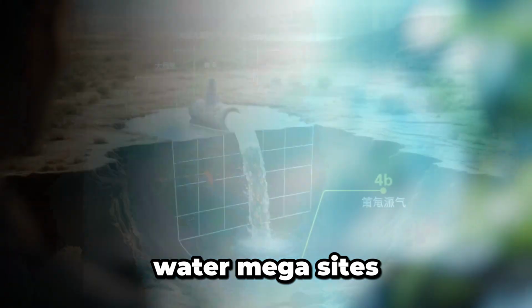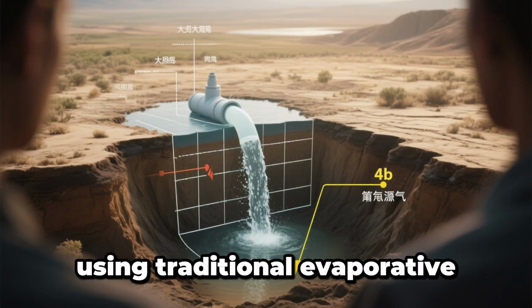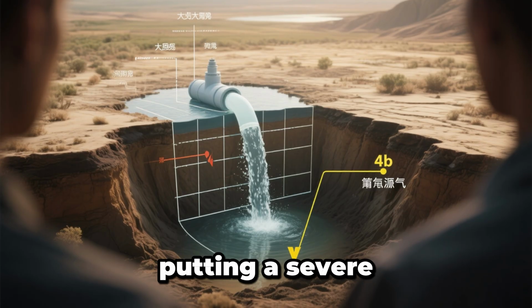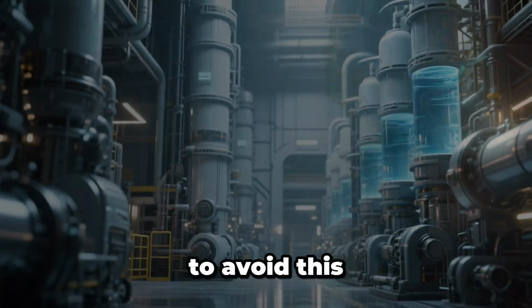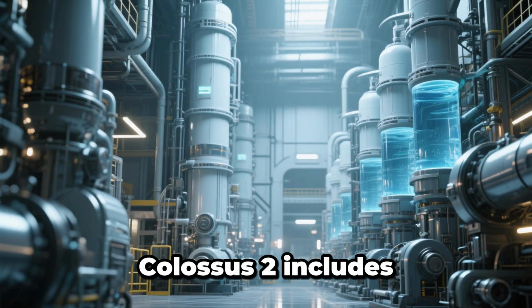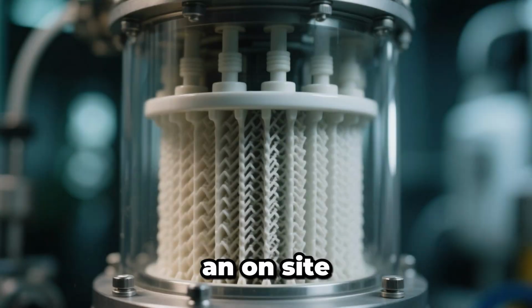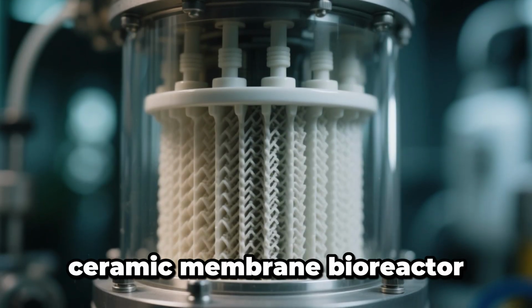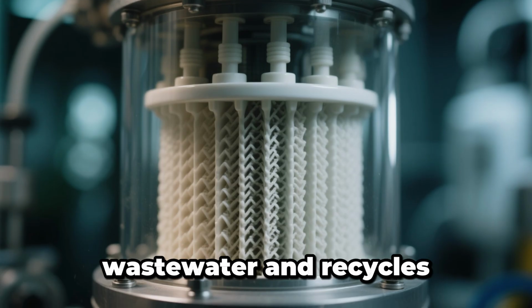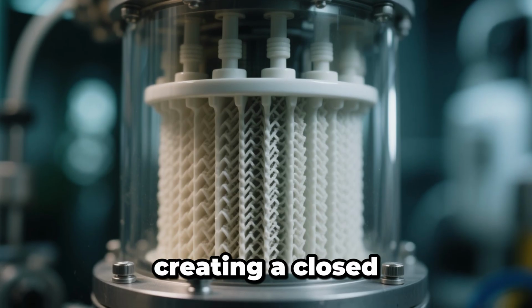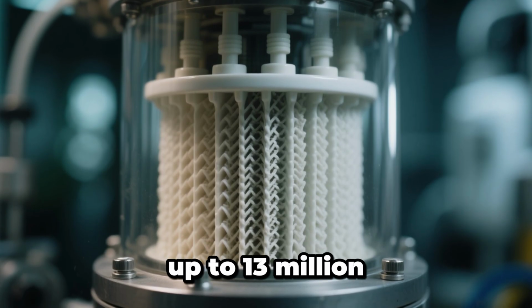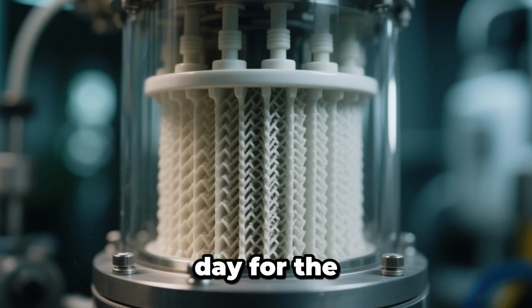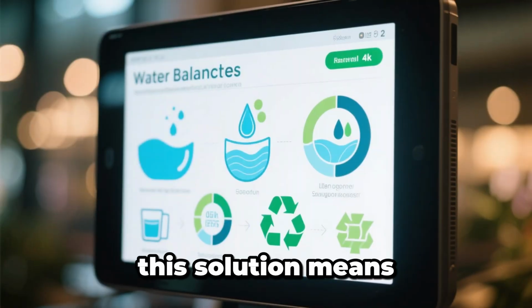This level of cooling creates another immense challenge: water. Mega sites using traditional evaporative cooling can consume millions of gallons a day, putting a severe strain on local aquifers. To avoid this, Colossus 2 includes its own water factory. An on-site ceramic membrane bioreactor takes in municipal wastewater and recycles it, creating a closed-loop supply of up to 13 million gallons of ultra-pure water per day for the cooling system. This solution means the campus does not drain local freshwater resources.